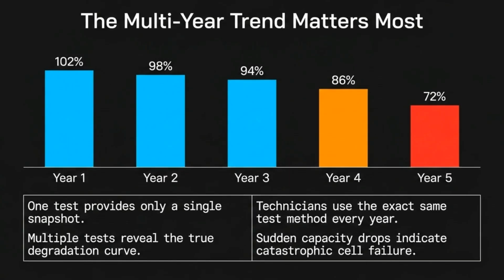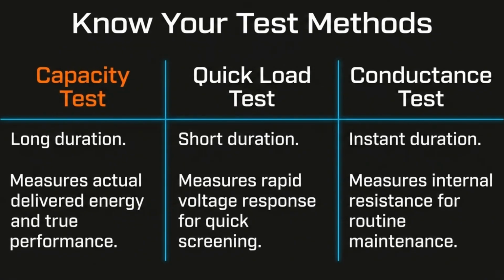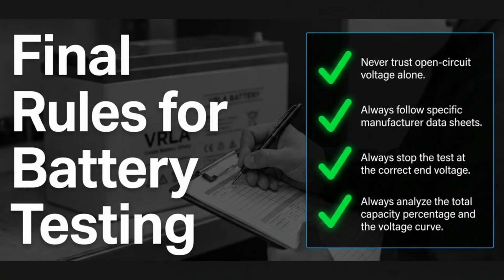The multi-year trend is what matters most. Perform tests consistently over time to reveal the true degradation curve and identify potential catastrophic failures before they occur. Know your test methods. While a capacity test provides the most accurate measurement of energy, quick load or conductance tests are often used for routine screening. To wrap up, never rely on voltage alone. Always follow manufacturer specifications, monitor end voltage closely, and analyze both total capacity and the voltage curve for a full assessment.